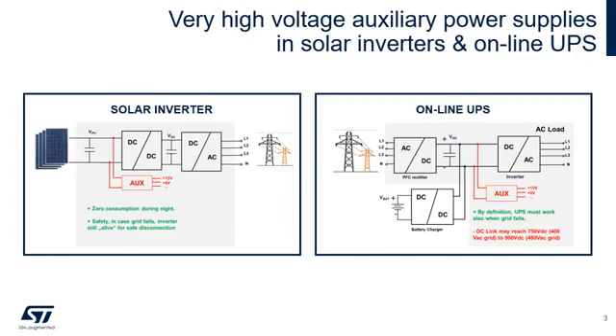Similarly, on large online UPS systems, the auxiliary power supply is needed to work when the grid fails, and is connected to the middle DC link. Both examples require the auxiliary power supply to be connected to very high voltages.